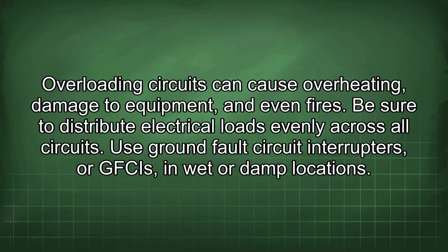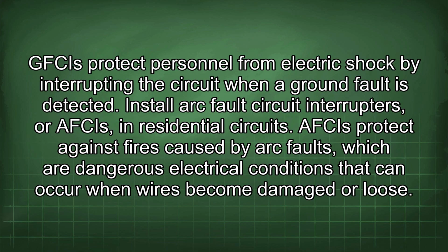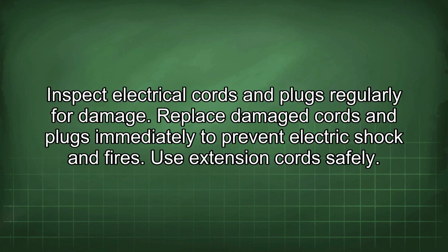Use ground fault circuit interrupters, or GFCIs, in wet or damp locations. GFCIs protect personnel from electric shock by interrupting the circuit when a ground fault is detected. Install arc fault circuit interrupters, or AFCIs, in residential circuits. AFCIs protect against fires caused by arc faults, which are dangerous electrical conditions that can occur when wires become damaged or loose. Inspect electrical cords and plugs regularly for damage. Replace damaged cords and plugs immediately to prevent electric shock and fires.